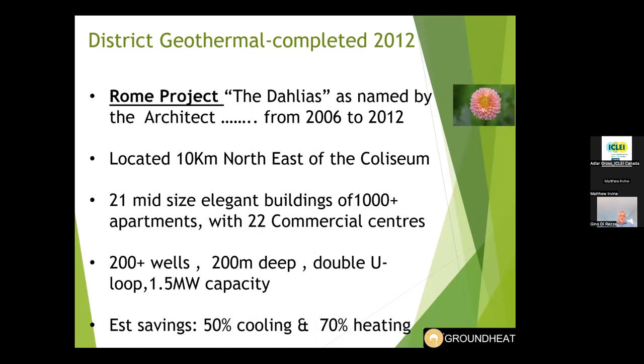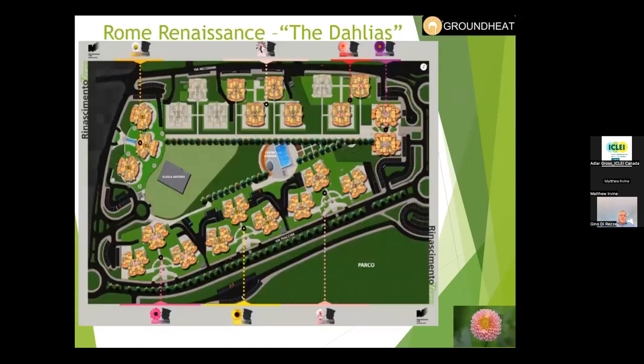We use 200-plus wells, 200 meters deep. In Europe, they always use two U-bends in the ground instead of one. Usually you pick up 15 to 20% more capacity. In this case, because of some diversity, the capacity for this project was in the area of 1.5 megawatts. The estimated savings is 50% in cooling and 70% in heating.